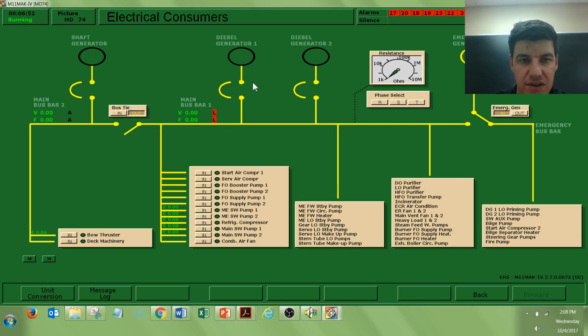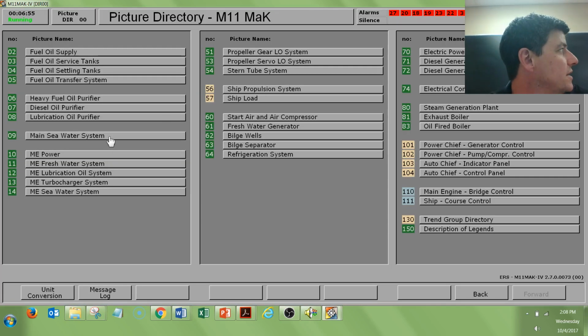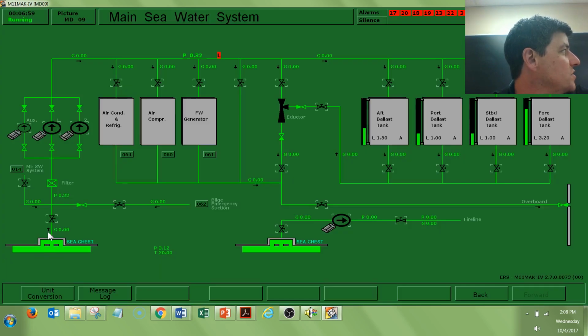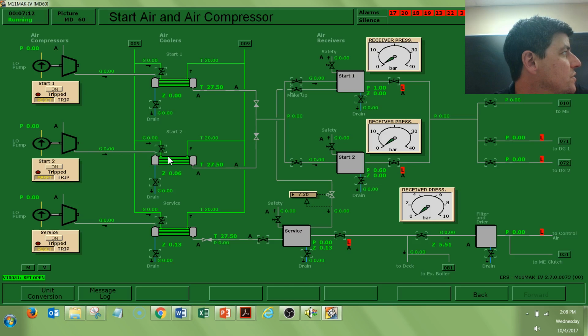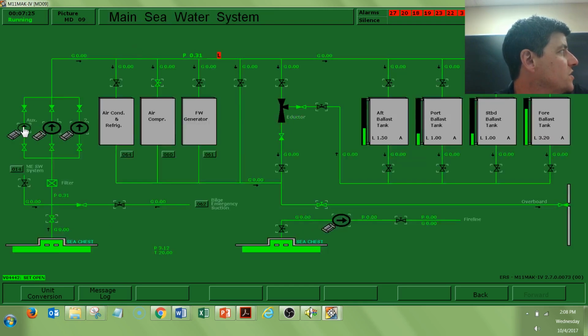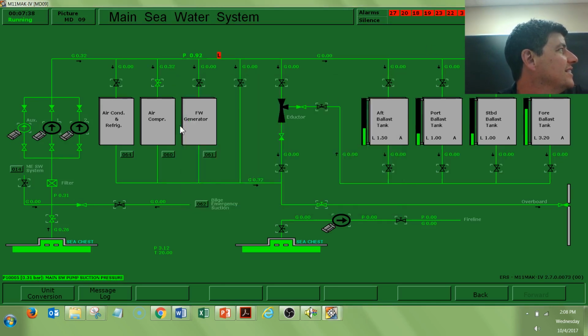Okay, so we'll transition over to our main seawater system. Our pathway starts at the sea chest, goes through a bank of pumps, through our air compression system, and eventually to overboard. On our air compressors, we have a cooler, which is going to allow our flow through our start air compressor 2, which we can run at this point. Our auxiliary pump is the one we can use. So turning that guy on, he is on and staying on, and ooh, do not want this to go up. All right.